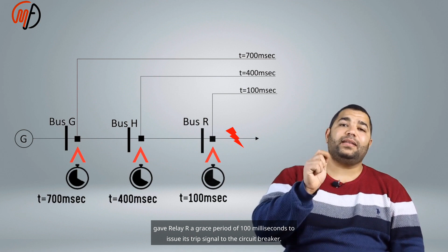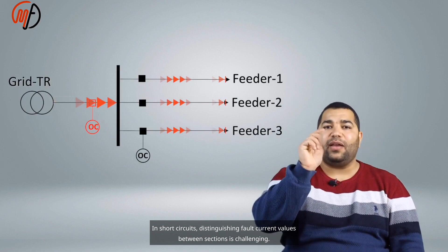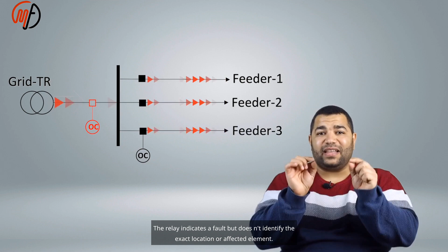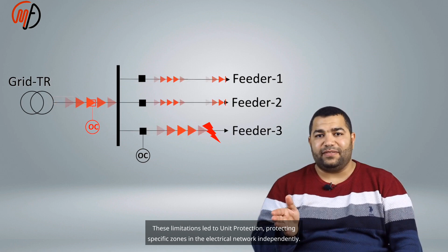Overcurrent relays can't pinpoint fault locations in transformers. They detect faults when current exceeds a set value. In short circuits, distinguishing fault current values between sections is challenging. The relay indicates a fault but doesn't identify the exact location or affected element. These limitations led to unit protection, protecting specific zones in the electrical network independently.